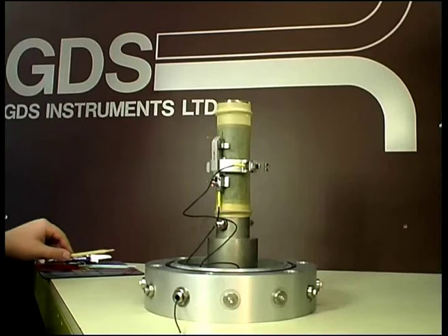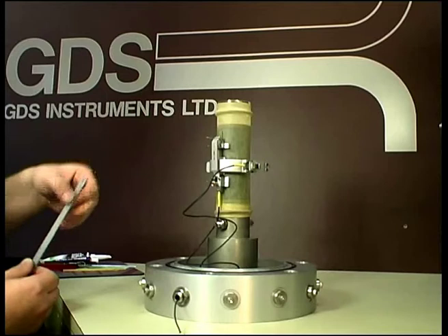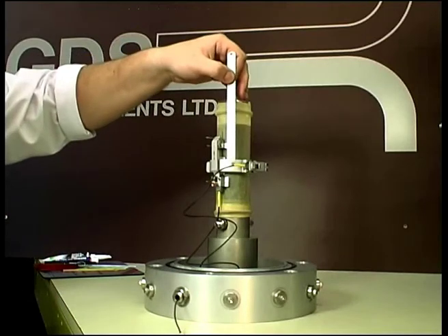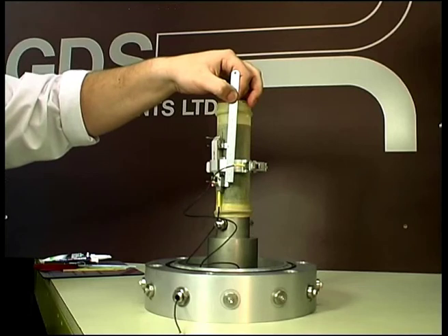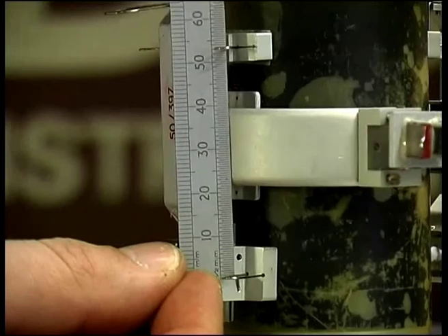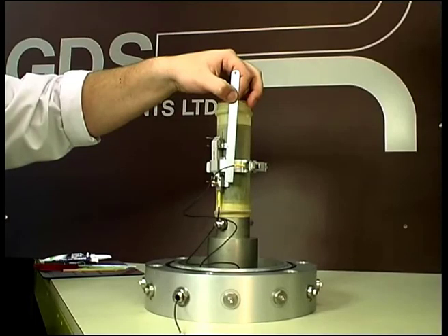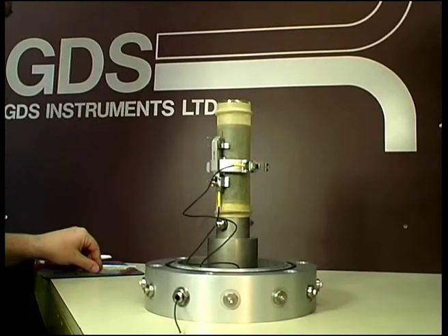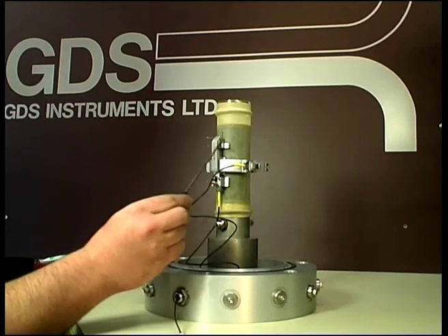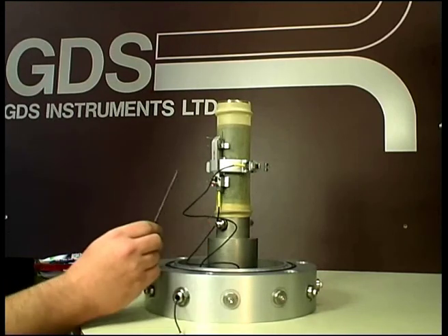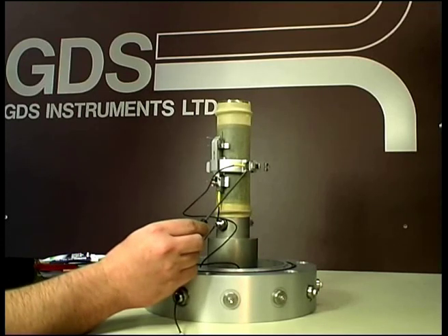Measuring the gauge length of the axial calipers in position between the centres of the pads is extremely important, as this measurement will be used in the final calculation of specimen axial strain. Remember also that the 2 to 1 ratio between the radial caliper pads and the radial transducer will mean that the measured displacement at the transducer will actually be equal to twice the diameter change.